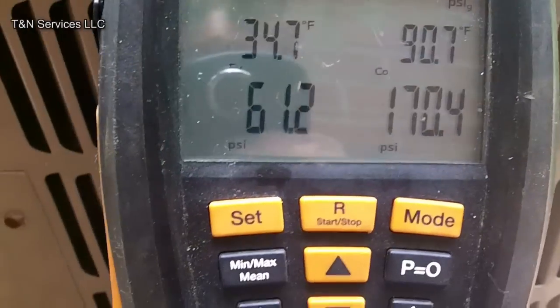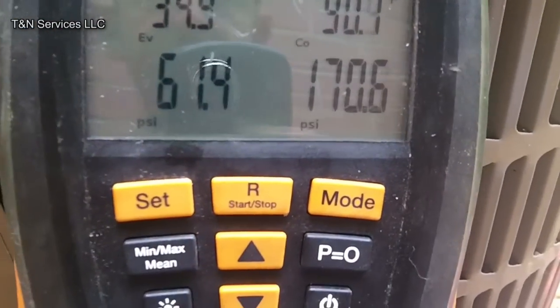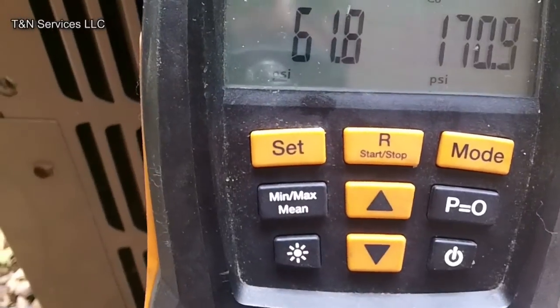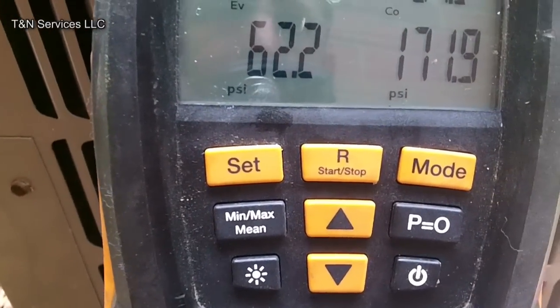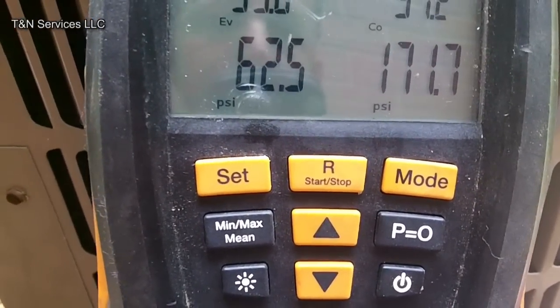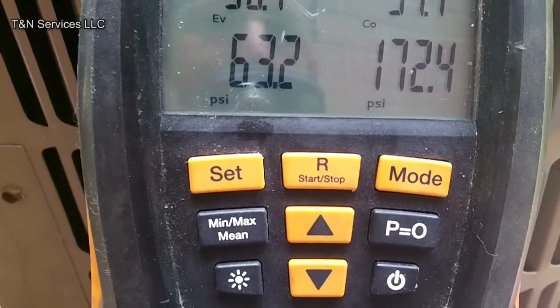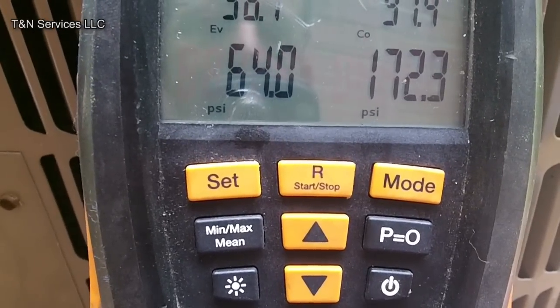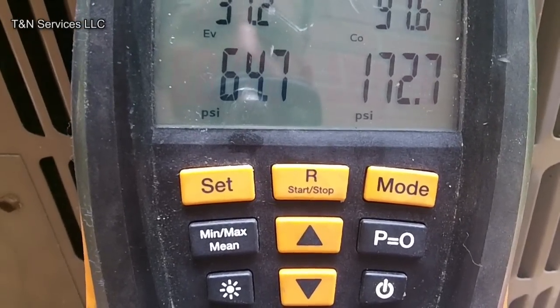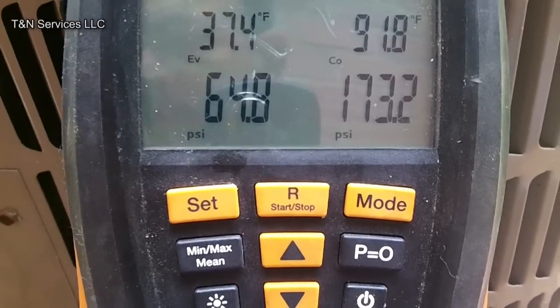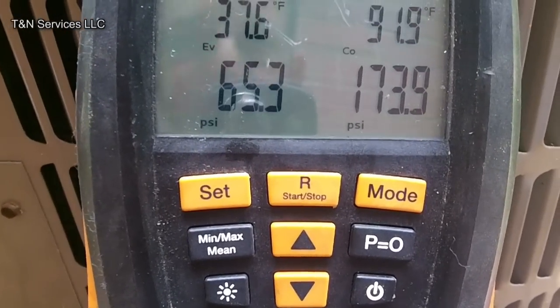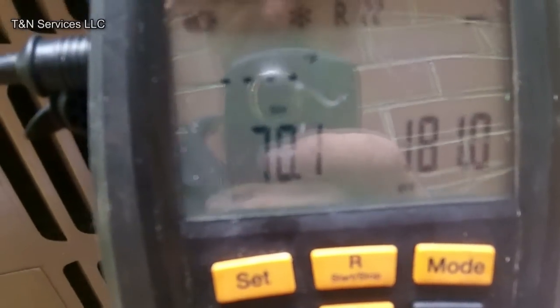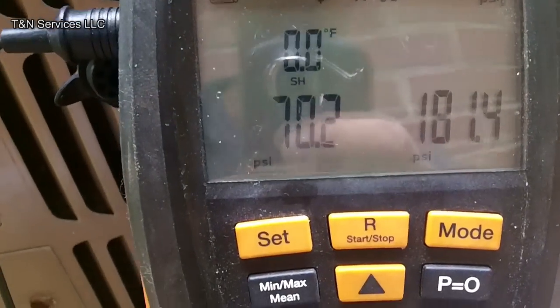But as you see, we got a 61-pound suction, 170 head, and I believe we will be, well, we're going to let it run for a few minutes, but I think we may be alright actually. So let's wait and get the probe on there so we can see what the temperature is. Alright, got my temperature probe on there, and as you see I got about a 70-pound suction, 0 degree superheat, and so it tells me it's overcharged.